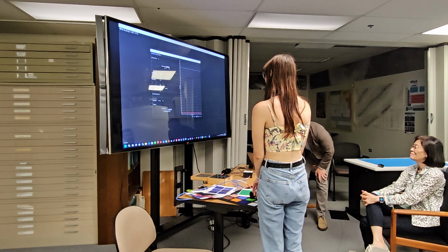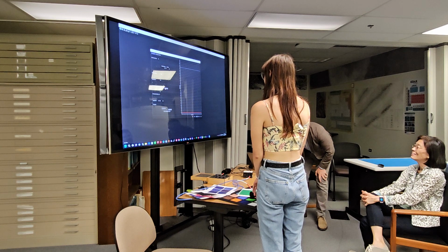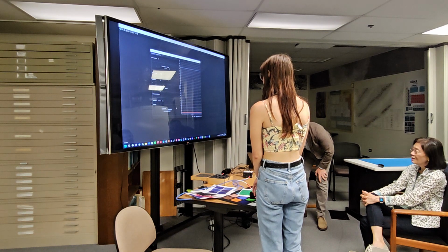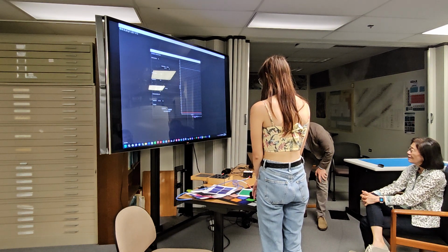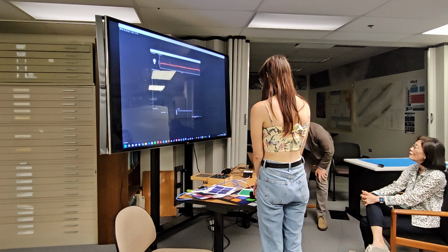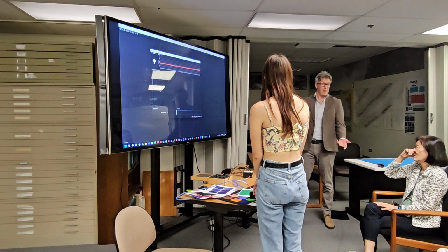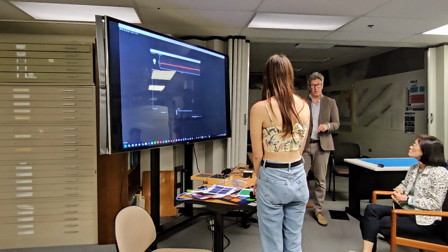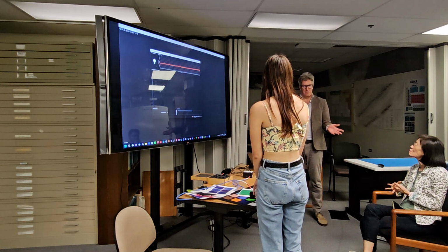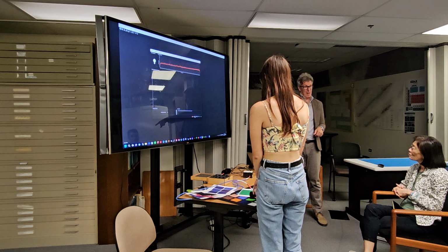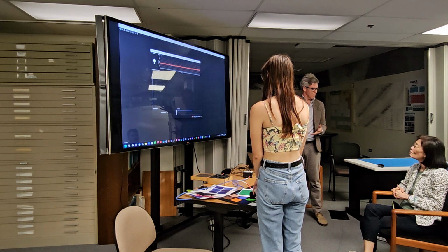Okay, so we will do our dark spectrum. Dark spectrum is installed. I turn this on. No need to know what that means. Right, so I've done that and that. Now I go to next. Now, honest, don't move, don't move, don't move. The next thing I'm going to do is store this reference spectrum, right? I want to know how much light is falling on all of my targets in the future. So I'm going to make a measurement of the light that comes back from that target, and we just optimize the integration time.